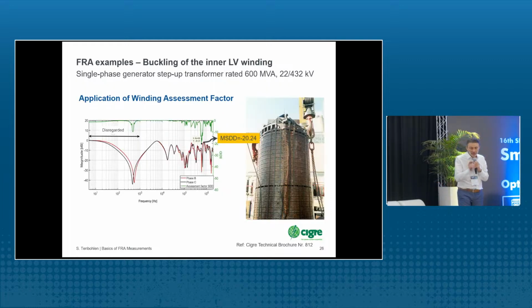Here we used the sliding window technique. Here we have the two curves. Here we see also a major difference, but this is, as I said before, the low frequency, and low frequency is due to the core magnetization. If you have a remanence of the core, then you can have a shift of this frequency. So this shift has to be disregarded. But here for the higher frequencies, we have a value of -20, which is lower than -5 in the negative range. That means we have a problem, and so the transformer was dismantled, and you could see here the buckling of the winding.